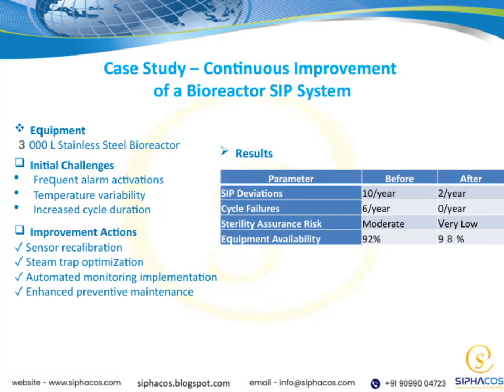Here's what we found after making some targeted improvements to the bioreactor SIP system. Before, we had 10 deviations a year, now just 2. Cycle failures dropped from 6 to 0. The risk to sterility went from moderate to very low. Equipment availability climbed from 92 to 98%. We tackled frequent alarms, temperature swings, and long cycles by recalibrating sensors, optimizing steam traps, automating monitoring, and stepping up preventive maintenance. These changes made a real difference.